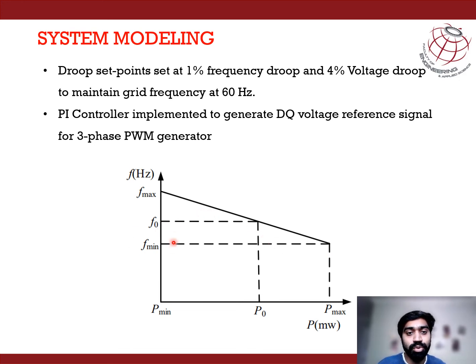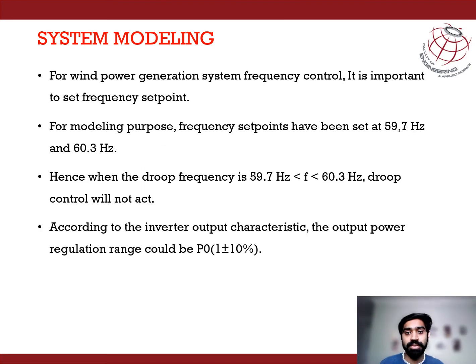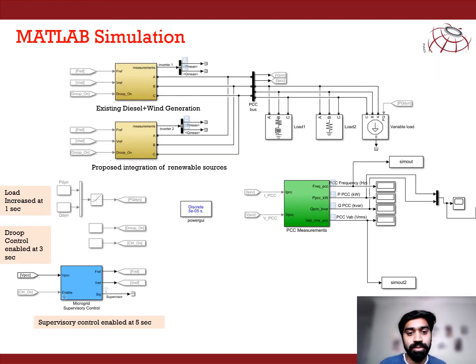So these are the two droop set points, F max and F minimum, set for our frequency regulation in MATLAB Simulink. As we have set the frequency droop set point at 1%, frequency can deviate from 59.7 Hertz to 60.3 Hertz. And according to the inverter output characteristic, the output power also can vary to 10% of its rated power output.